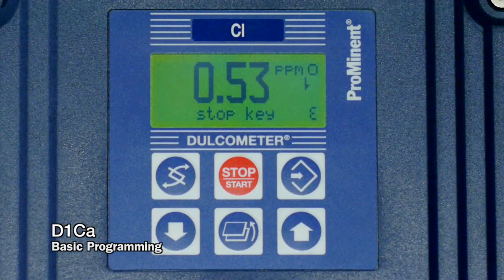Calibrating the unit is telling the D1C how much residual is actually in your process water. Before you do your calibration, be sure that flow is going past the sensor. The D1C unit is wired to the sensor, power is on, and we do actually have a residual in the water, until that sensor has stabilized and the reading isn't jumping up or down any longer. Once it's stabilized, we can do our calibration.